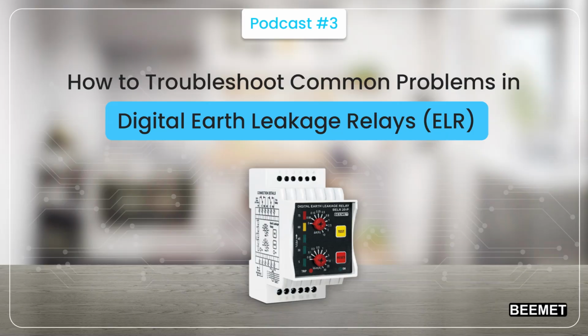If something goes wrong, you must check each component separately. Issues may arise from overloaded CTs, the algorithm responding to noise instead of leakage, faulty wiring, or loose terminals. It is therefore important to check fault assumptions before using them.